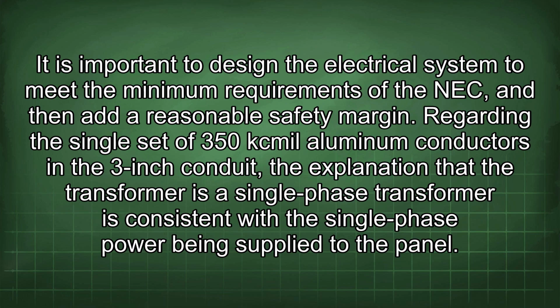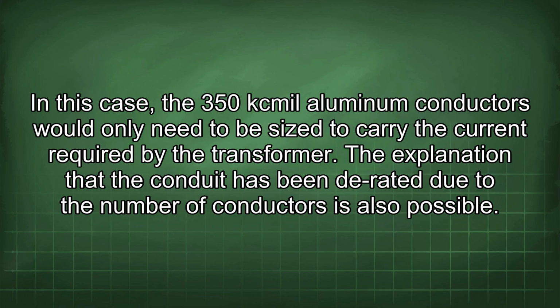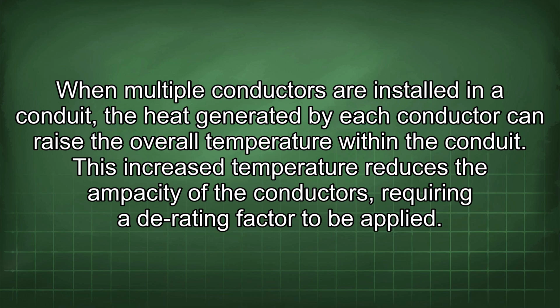Regarding the single set of 350 kcmil aluminum conductors in the 3-inch conduit, the explanation that the transformer is a single-phase transformer is consistent with the single-phase power being supplied to the panel. In this case, the 350 kcmil aluminum conductors would only need to be sized to carry the current required by the transformer. The explanation that the conduit has been derated due to the number of conductors is also possible. When multiple conductors are installed in a conduit, the heat generated by each conductor can raise the overall temperature within the conduit. This increased temperature reduces the ampacity of the conductors, requiring a derating factor to be applied.